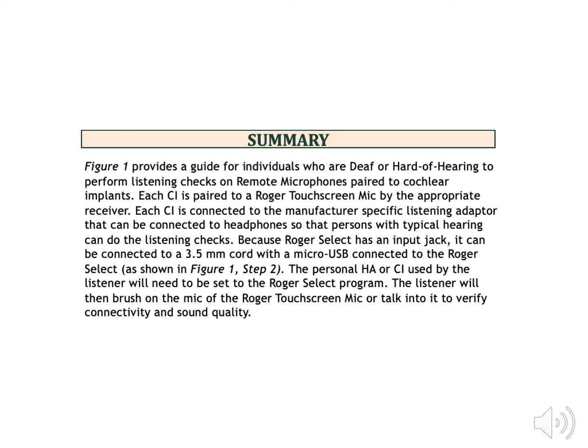Figure 1 provides a guide for individuals who are deaf or hard of hearing to perform listening checks on remote microphones paired to cochlear implants. Each cochlear implant was paired to a touchscreen mic by the appropriate receiver. The CI is then connected to the manufacturer's specific listening adapter that can be connected to headphones so persons with typical hearing can do the listening checks. Because the Roger Select has an input jack, it can be connected to a 3.5mm cord with the micro USB connected to the Roger Select. The personal hearing aid or cochlear implant used by the listener was then set to the appropriate program, and the listener would then brush on the microphone of the Roger touchscreen mic or talk into it to verify the connectivity or sound quality. Another person can also talk into the Roger touchscreen and walk away for more accuracy.